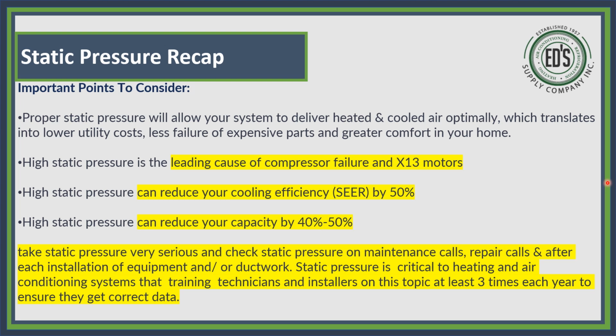So we went to look at the unit, and we got there. We checked our static pressure, and what we found was the blower speed on AC was low, it was in medium. So we moved it up to high, which is 5, and then we took our static pressure reading and looked at the install manual chart, and the chart told us at that static pressure reading that in AC we were blowing out 850 CFMs. That's great for a 2-ton. We did the same thing in the heat mode, but what we found out was in heat mode, that system was only putting out 445 CFMs.